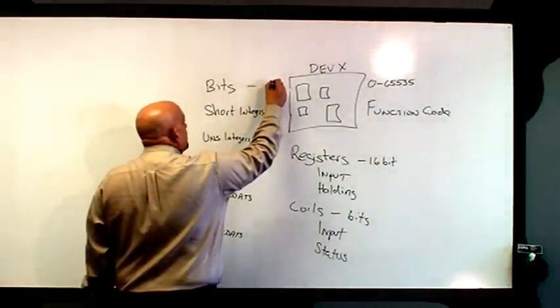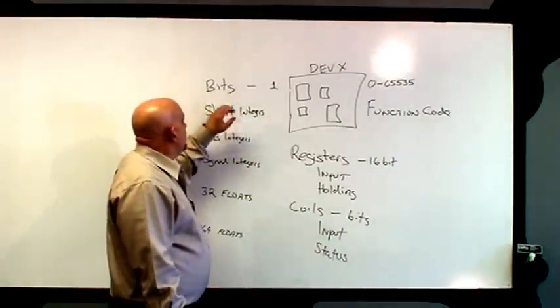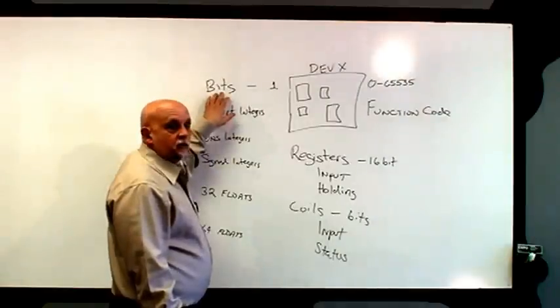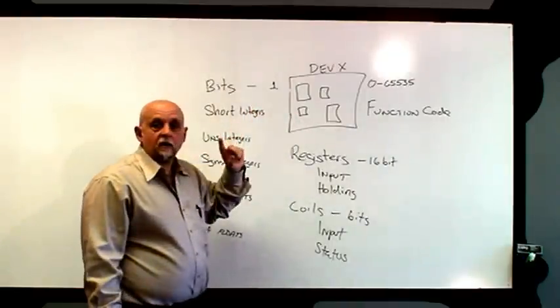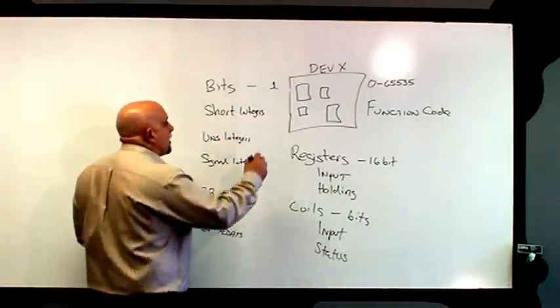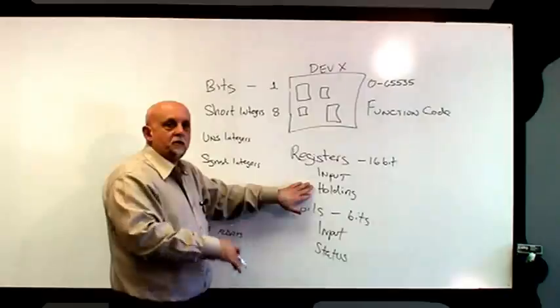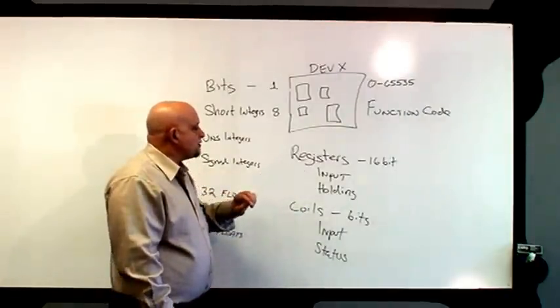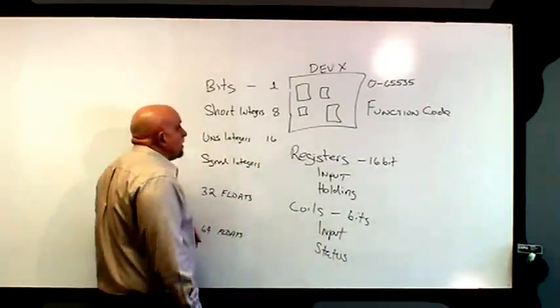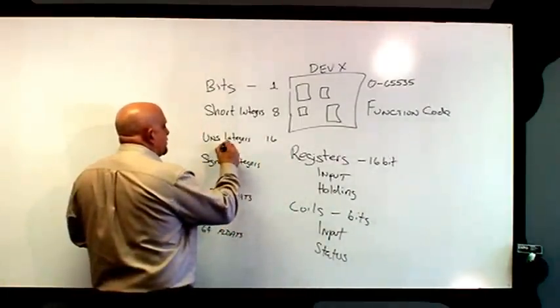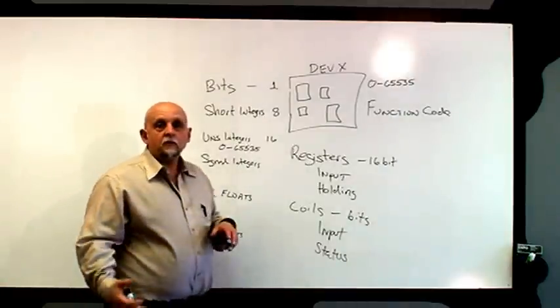Bits, of course, are single-bit and easily map into the coil space. So if you've got something like a relay you're going to turn on and off, you can represent it as a space a Modbus master can access by just allocating a coil — no problem. Short integers are actually 8 bits, so they fit into a register with the top half of the register always being zeros — no big deal. Unsigned integers are 16 bits, and an unsigned register goes from 0 to 65,535, so that's no problem to store there.